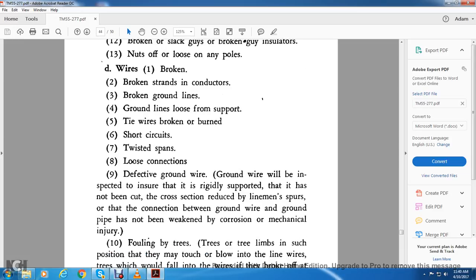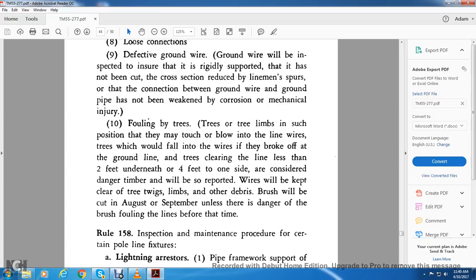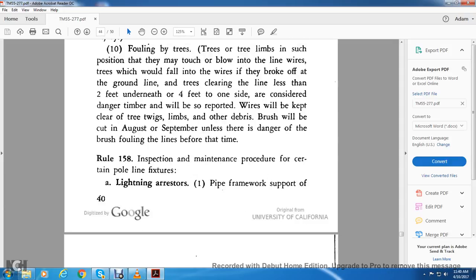9. Defective ground wire. It will be inspected to ensure that it is rigidly supported, that it has not been cut at the cross section reduced by the lineman's spurs, and that the connection between the ground wire and grounded pipe has not been weakened by corrosion or mechanical injury. 10. Fouling by trees or tree limbs in such a position that they may be touched or blown into the line wires, or a tree which would fall into the wires or break off at the ground line. The tree clearing of the lines is less than 2 feet underneath and 4 feet on the side, and considered dangerous timber will be so reported. Wires will be kept clear of trees, twigs, limbs, and other debris. Brush will be cut in August and September, unless the danger of brush fouling the lines exists before that time.